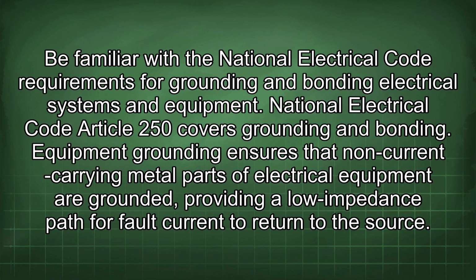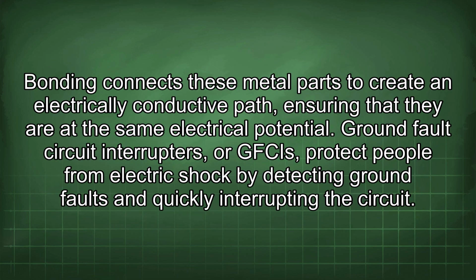Equipment grounding ensures that non-current carrying metal parts of electrical equipment are grounded, providing a low impedance path for fault current to return to the source. Bonding connects these metal parts to create an electrically conductive path, ensuring that they are at the same electrical potential.